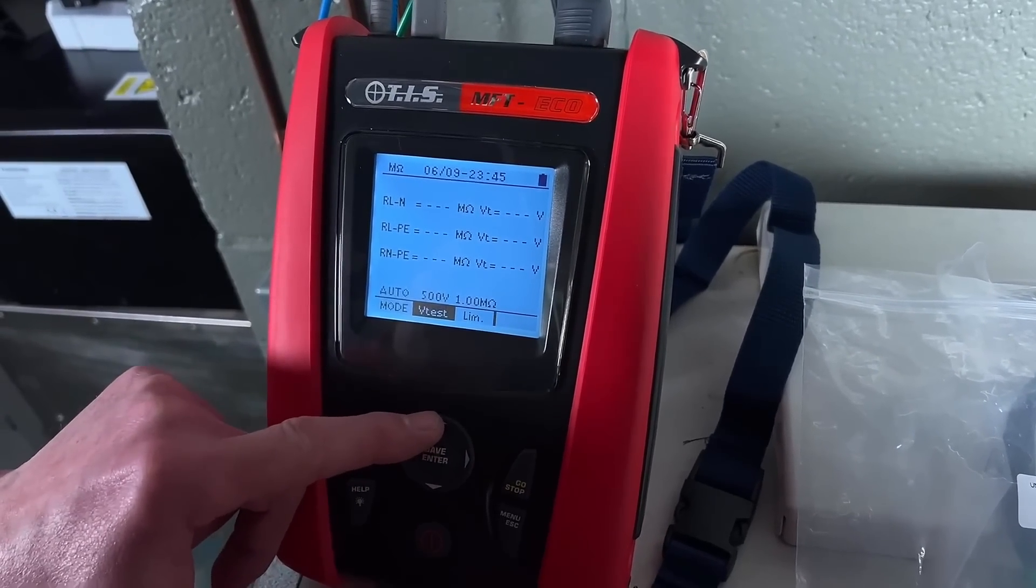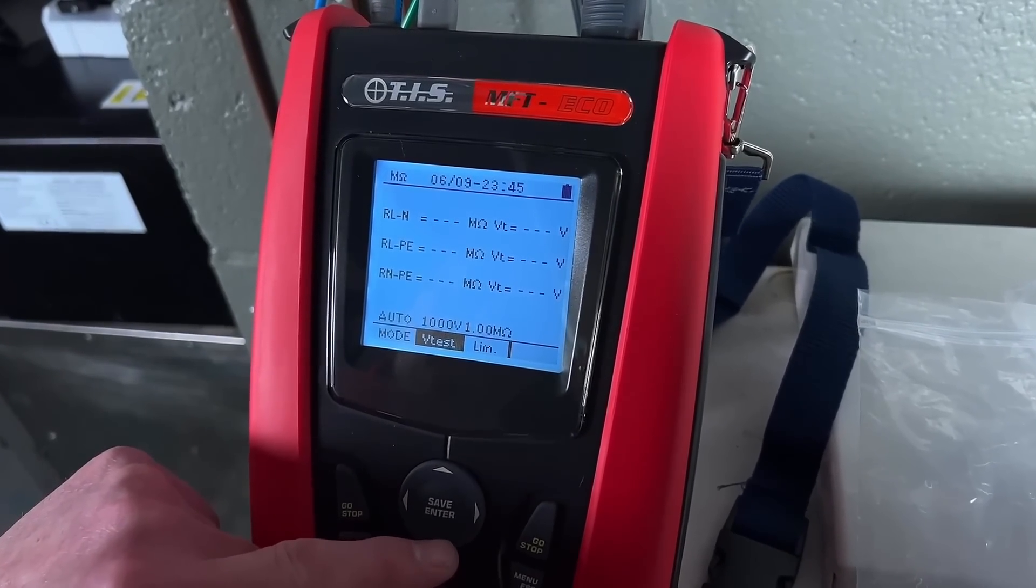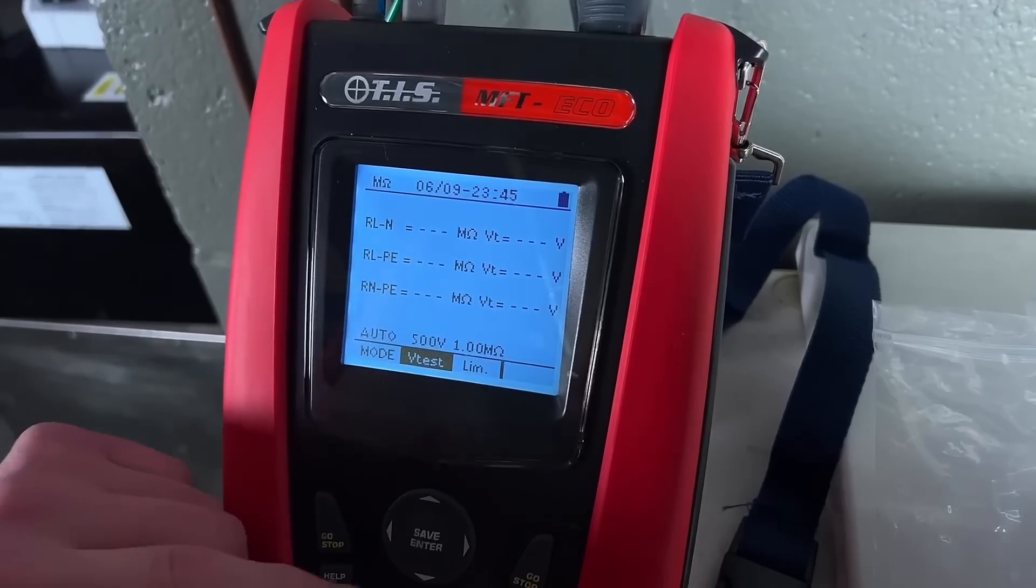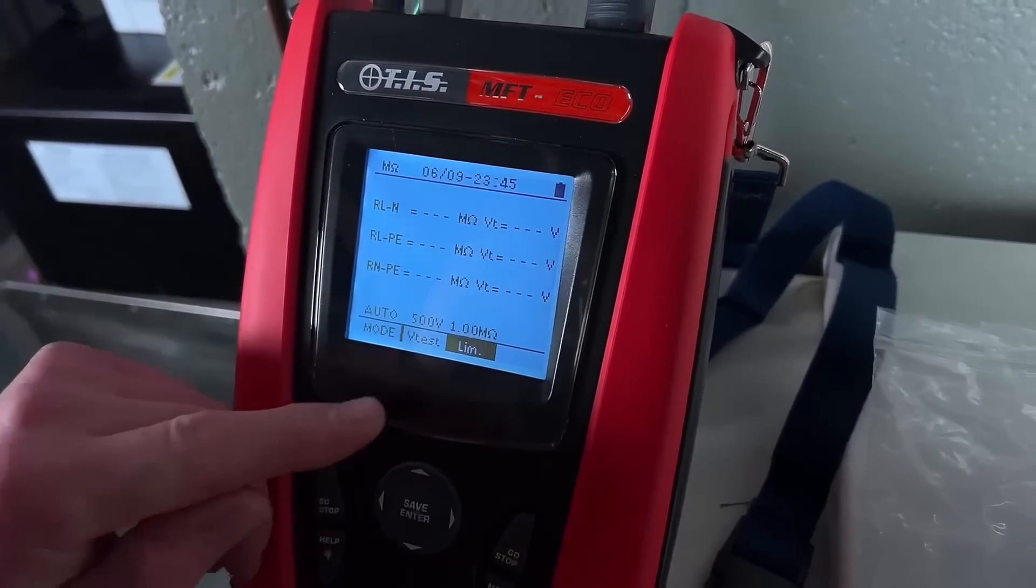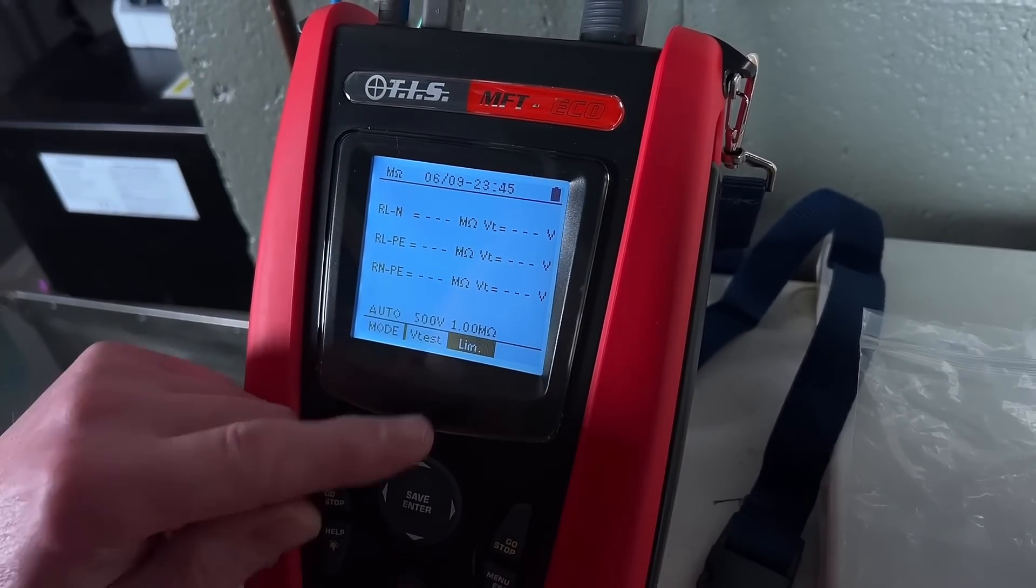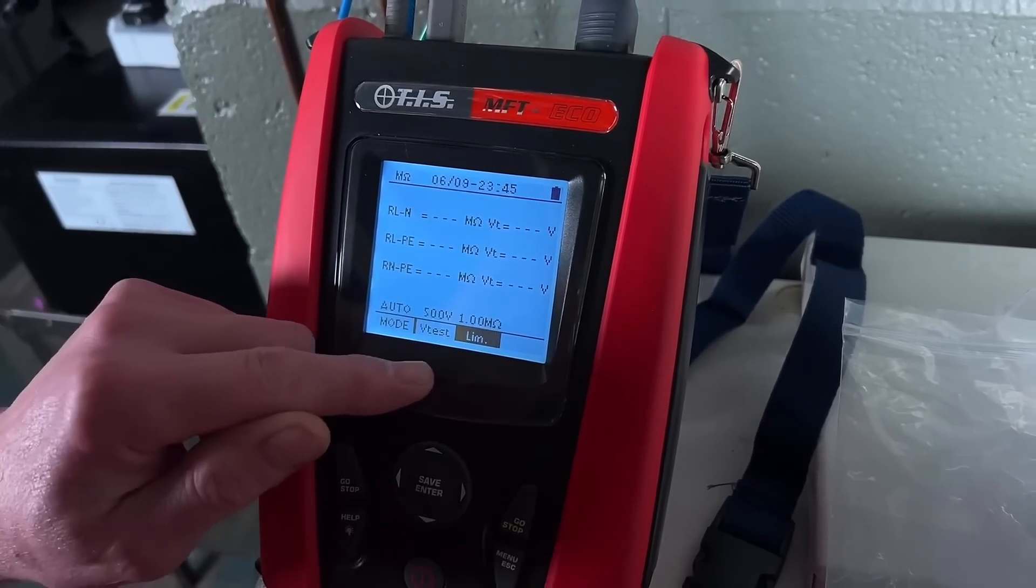I've also set it here to 500 volts, that's the test voltage in DC. I could have been at 250, could have been at a thousand, and anywhere in between. Then I've got it here set to what I want it to be, its pass value, and I've got that as one mega ohm. If I've got lower than one mega ohm, it will come up as a fail.